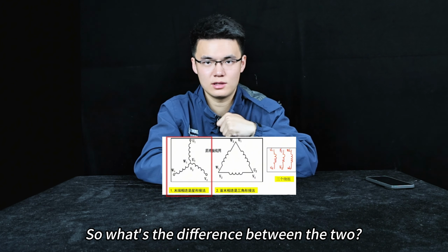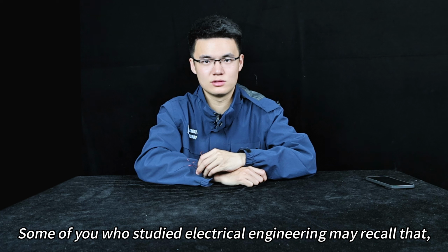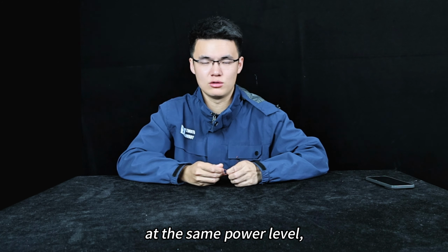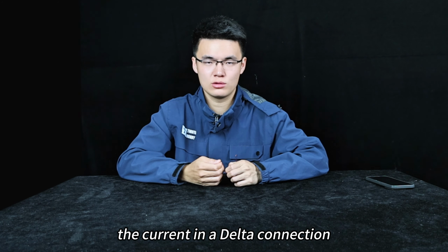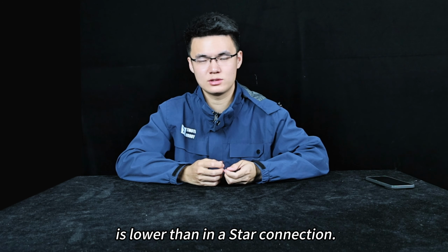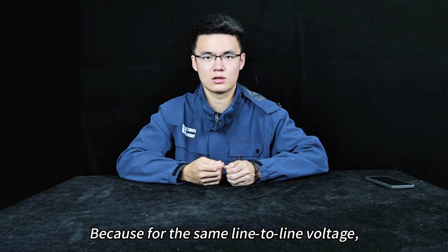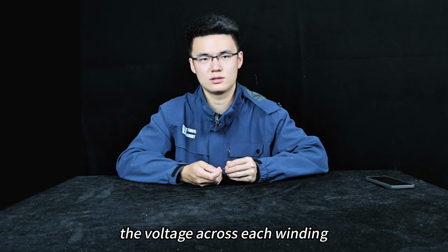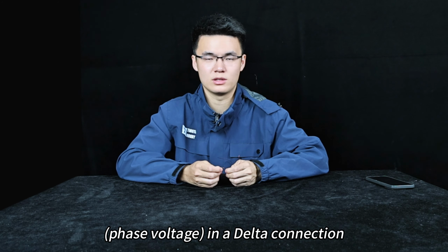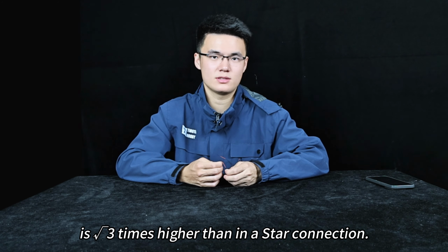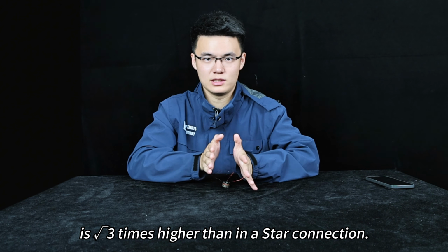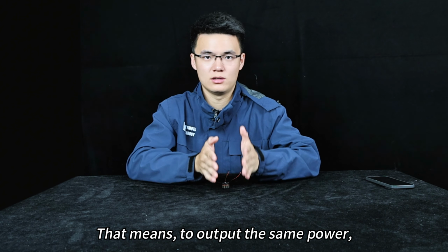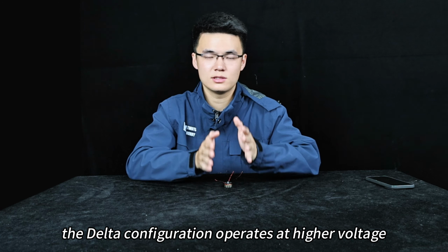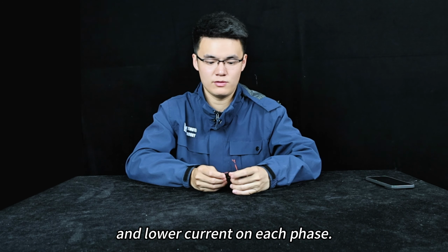So what's the difference between the two? Some of you who studied electrical engineering may recall that, at the same power level, the current in a delta connection is lower than in a star connection. Why is that? Because for the same line-to-line voltage, the voltage across each winding (phase voltage) in a delta connection is square root 3 times higher than in a star connection. That means, to output the same power, the delta configuration operates at higher voltage and lower current on each phase.